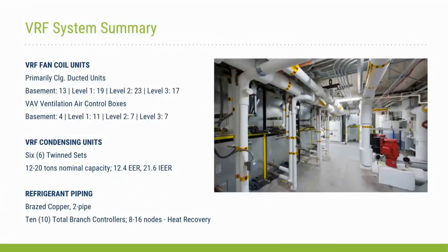So we used energy modeling to look at the variety of systems that Jason showed on the screen, even from the pre-award phase. We're looking at what provides best value to GSA to select. The radiant cooling and heating system actually came in a close second to the VRF system. The VRF system had the best overall life cycle cost out of all the systems considered. But really, one of the biggest drivers is just its ability to be fit within this historic building from the early 1900s.